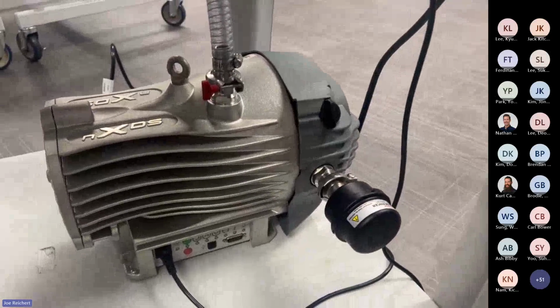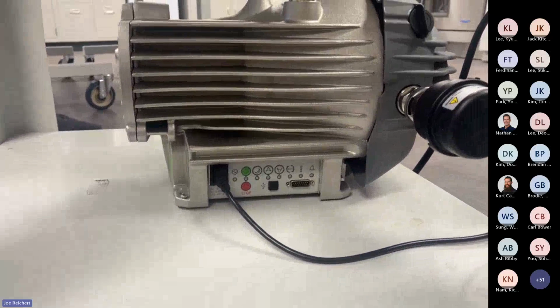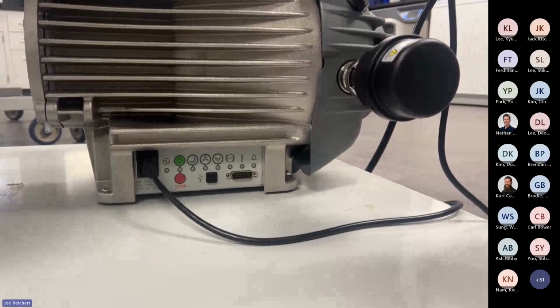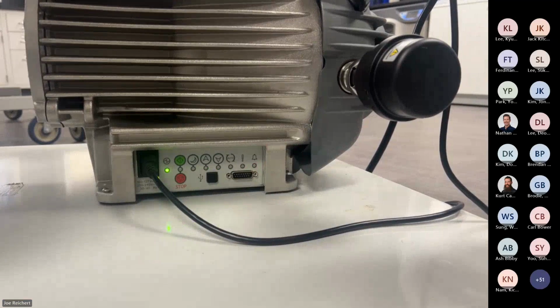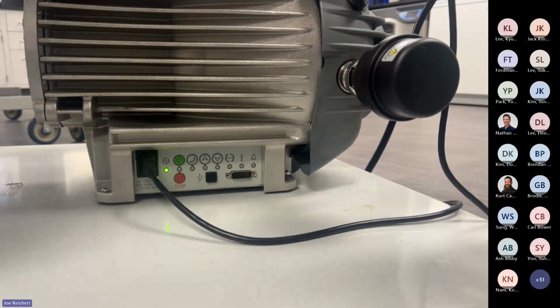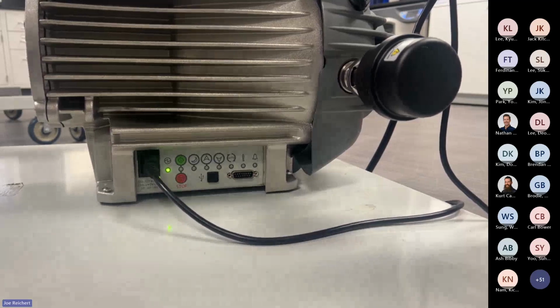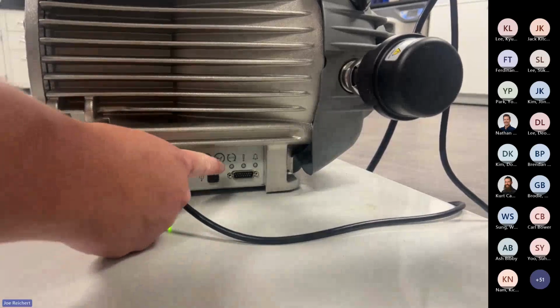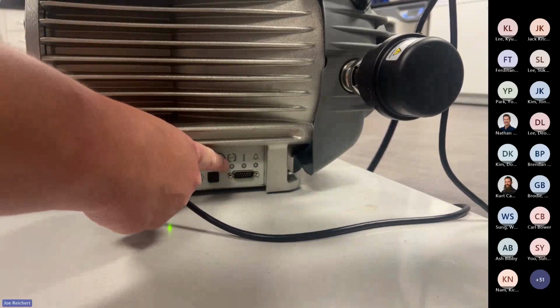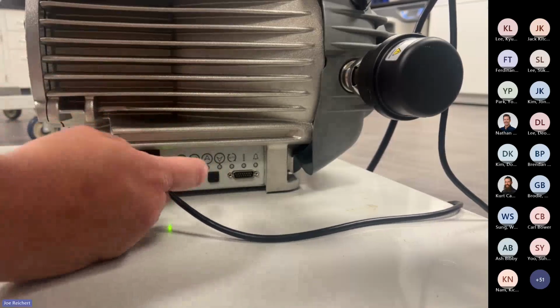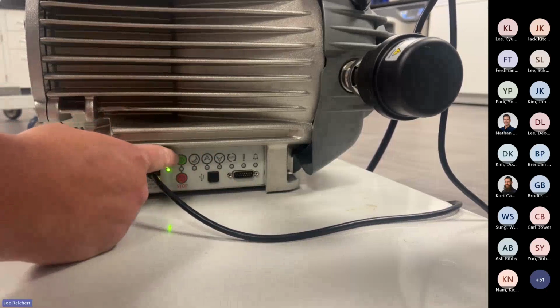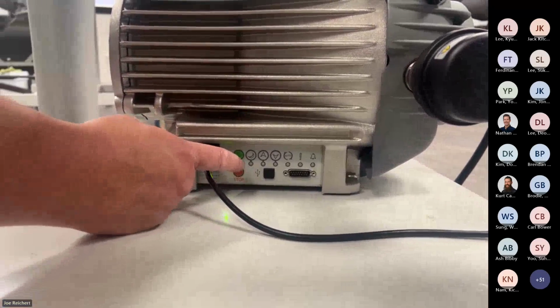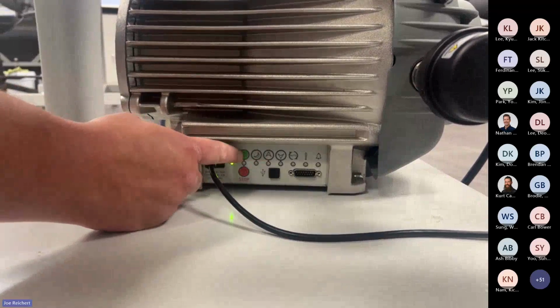So you either hit the green button and turn it on, but I'll turn on the vacuum pump so that we can get the light to turn on. If you notice, the light's on, but the pump did not come on. I know it's hard to hear it with my earbuds on. It kind of takes away the background noise, but it is not on. So to turn it on and to put it into auto mode, you'll see a little indication here that says auto, and then there's a light just below it. To turn it on to auto, you press and hold the green button or the red button. You could do either one. You hold it for at least 8 seconds, and then that light will come on.